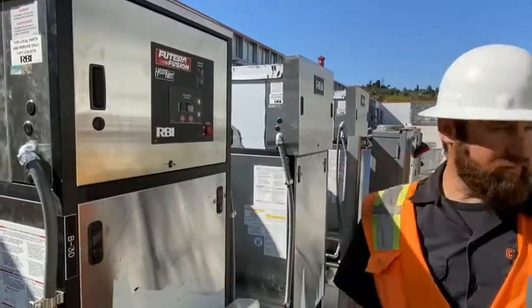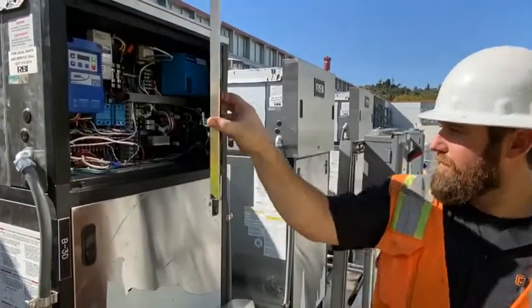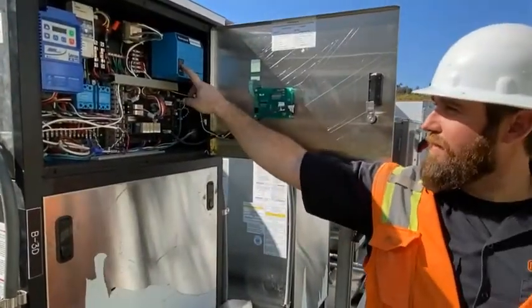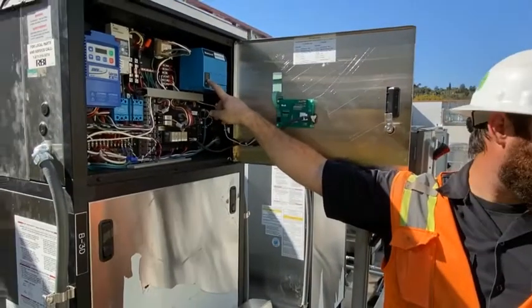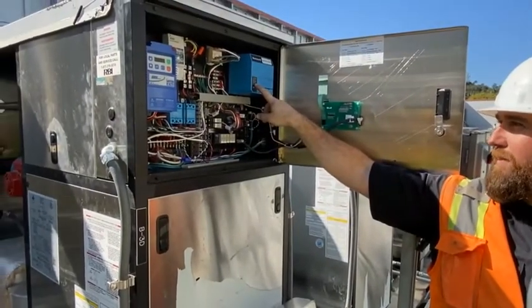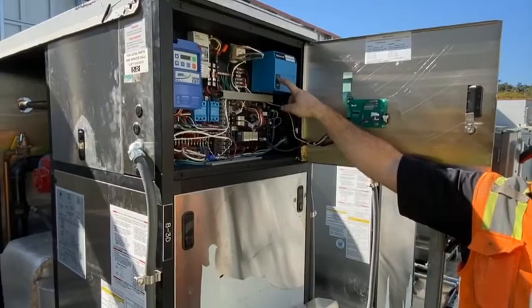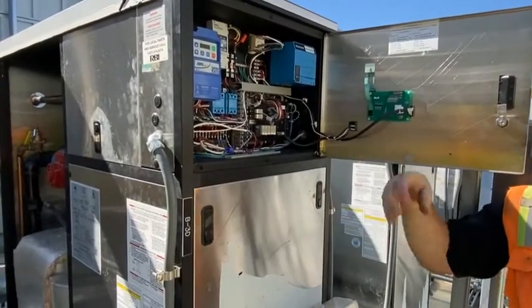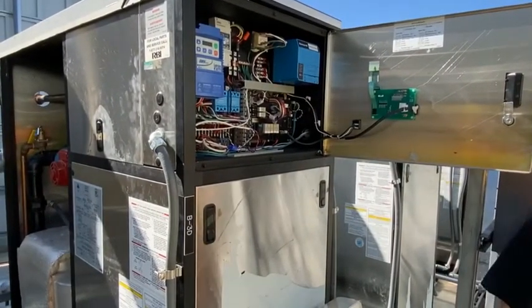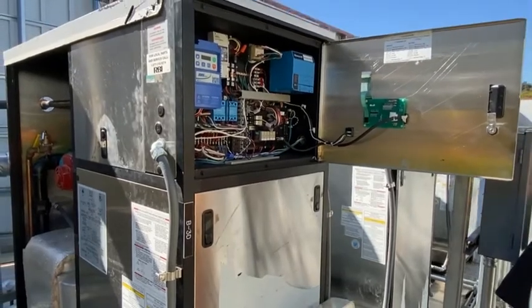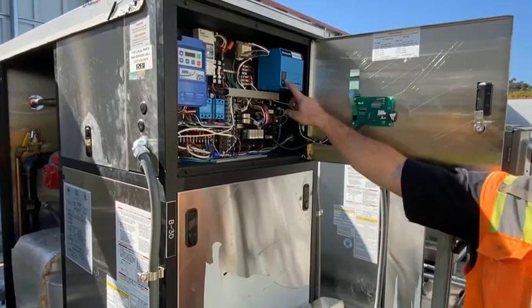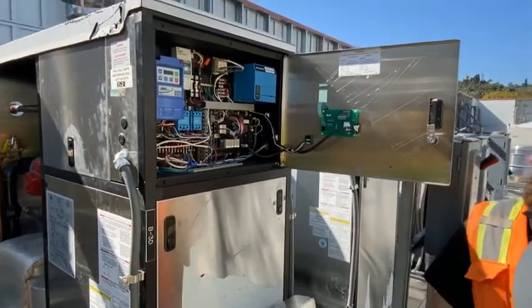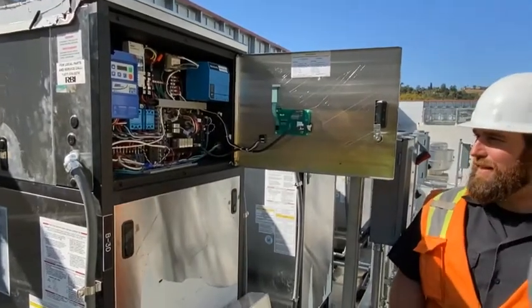Is that red light indicating a flame or a failure? This one is on flame, and it's a main flame, since the yellow one's lit up as well. That flame will be on as well when the pilot turns on. It's just the UV scanner picking up a flame. Okay, I just usually figure when you get red, that's an indication it's going to fail. Right, so you just have to worry about the very bottom. Yep, there's flame inside.